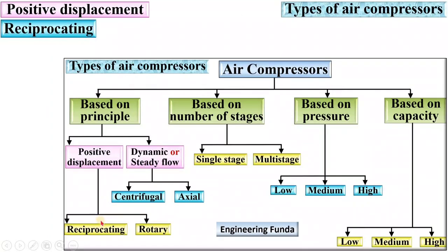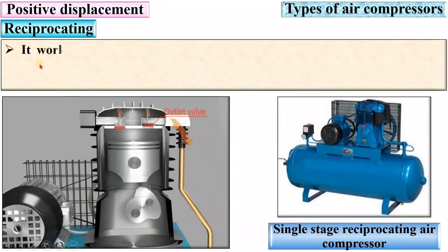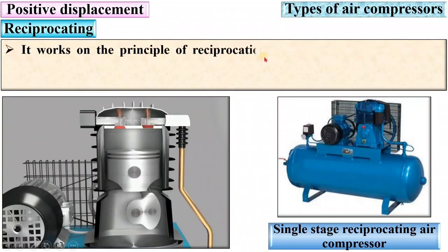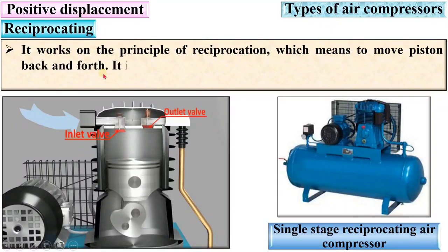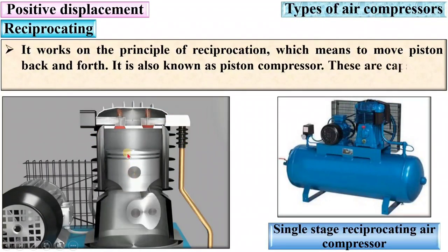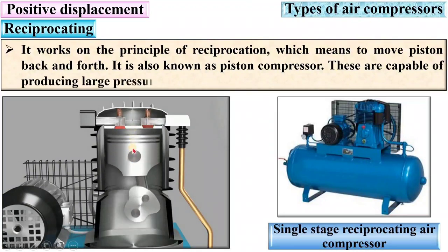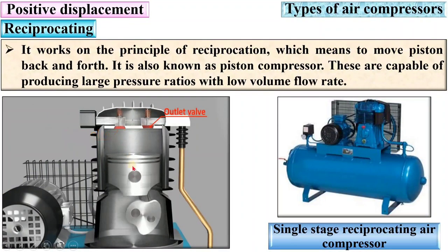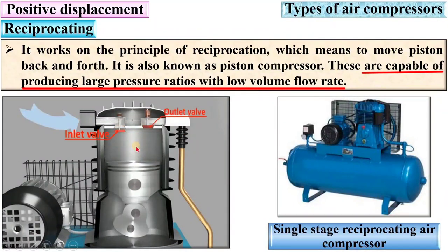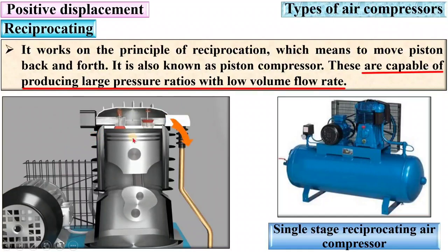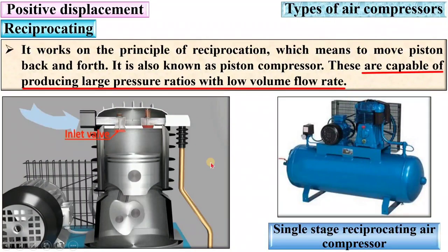Positive displacement is further classified as reciprocating and rotary compressor. The reciprocating compressor works on the principle of reciprocation, which means moving the piston back and forth. The piston reciprocates inside the cylinder — that is why it is called a reciprocating air compressor. These are capable of producing large pressure ratio with low volume flow rate.